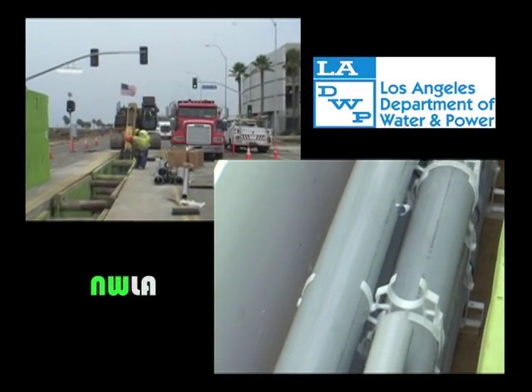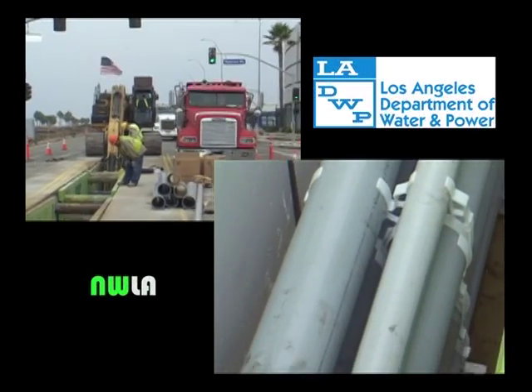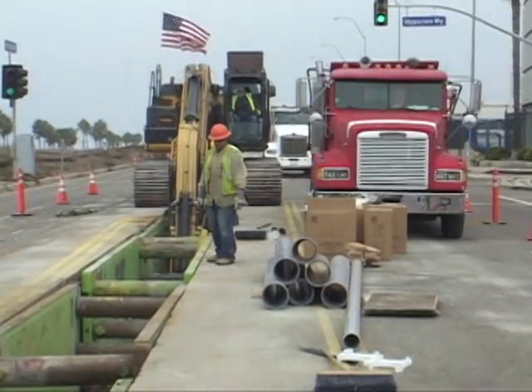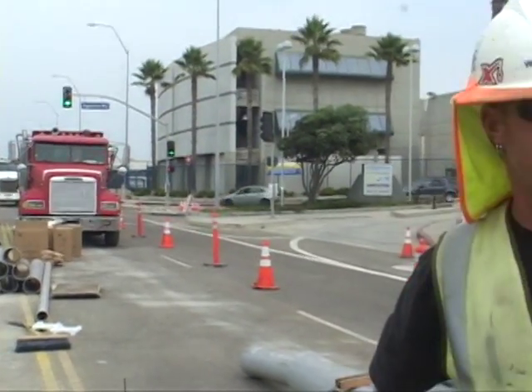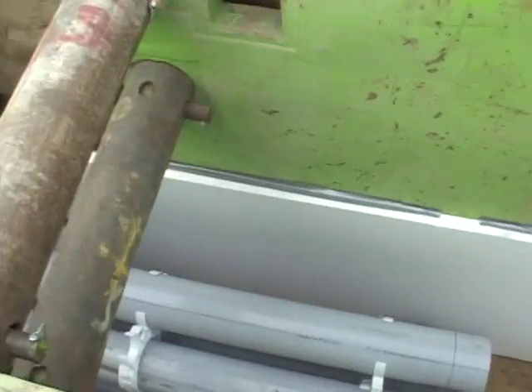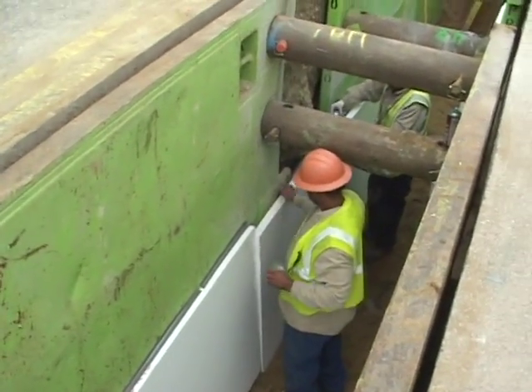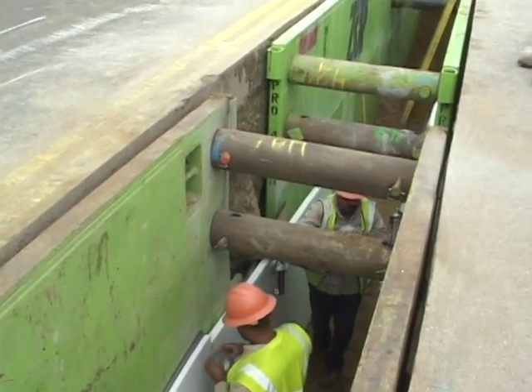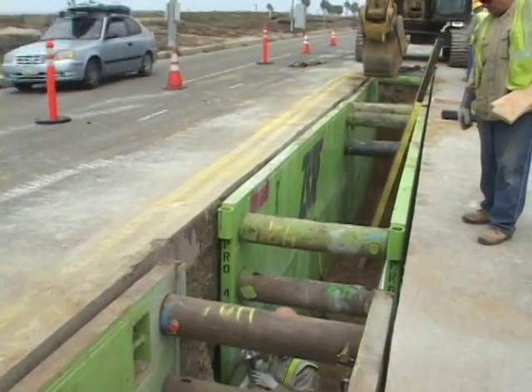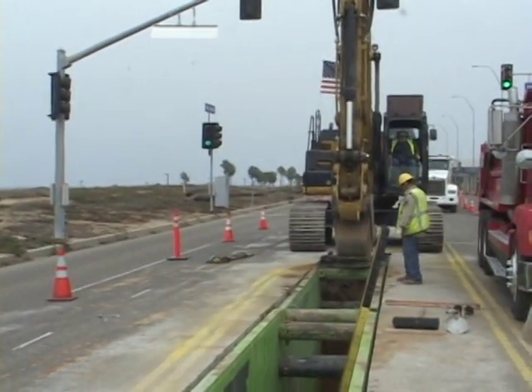And how far is this job going? My portion here is approximately 150 feet north of Imperial for a total of about a mile and three. How many cables and how much conduit is being installed below ground? Right now there are six eight-inch conduits and two four-inch traveler communication conduits. We're actually building two independent 230 kV systems simultaneously.